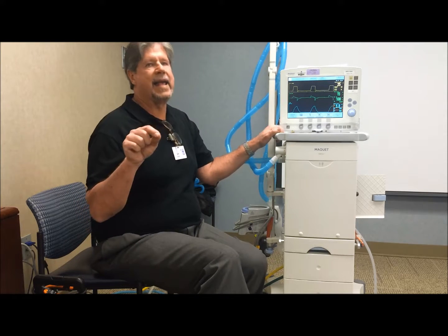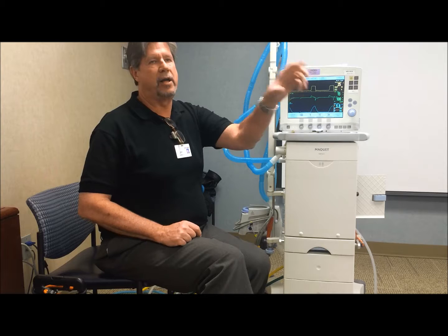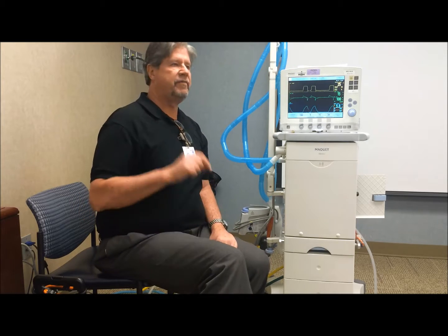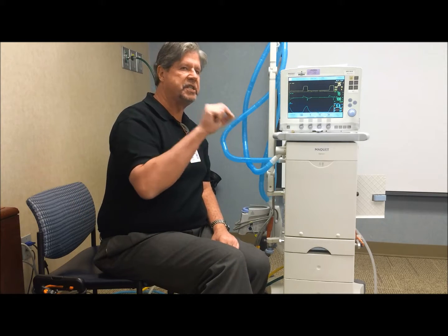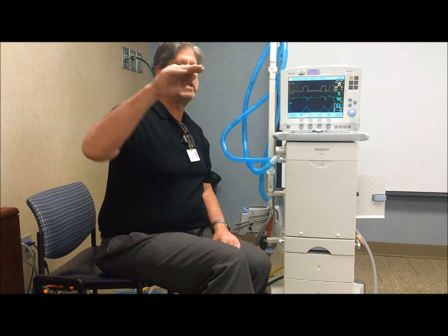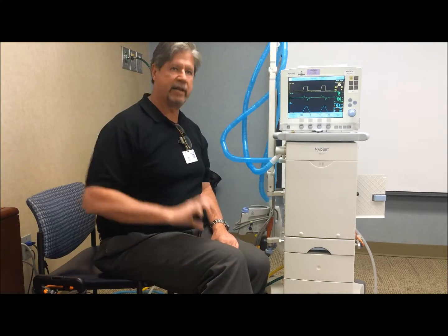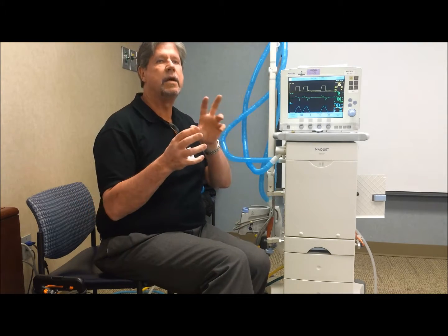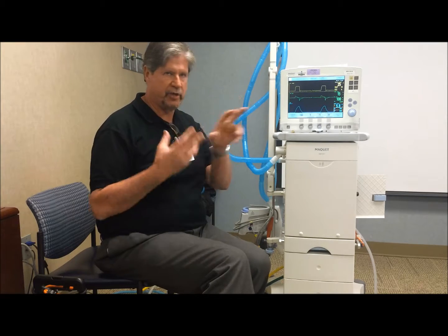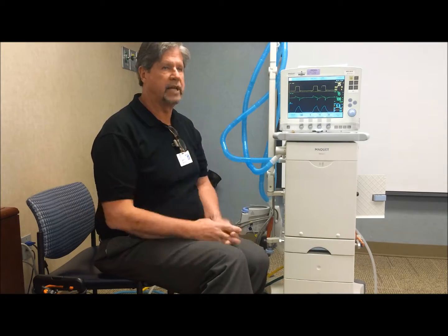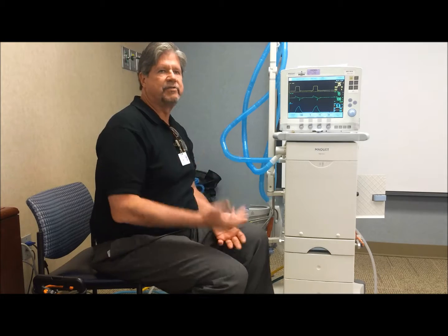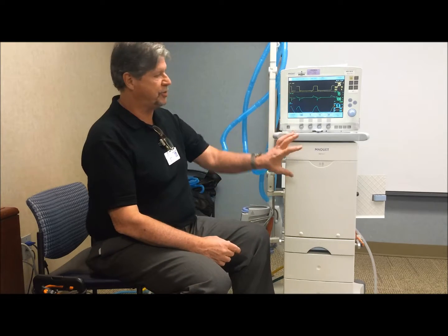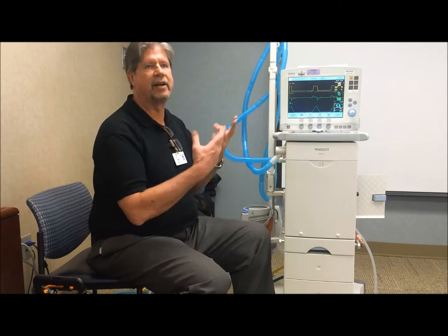And if you did that, and it was the same as the inhaled tidal volume, then you didn't have any leaks. But if you multiplied the 200 cc's times 1.5 and it didn't equal the inspiratory tidal volume, then you had a leak. And it wasn't the density issue causing that difference, it was an actual leak. So there was this jury rigging that you had to do, and some hospitals even had a little chart when using Heliox to do it.